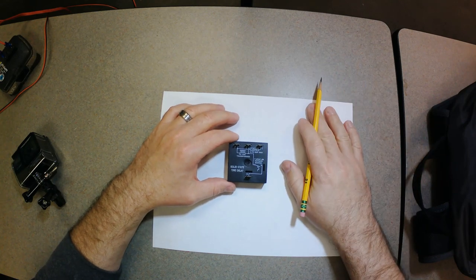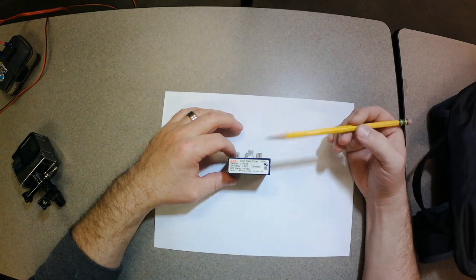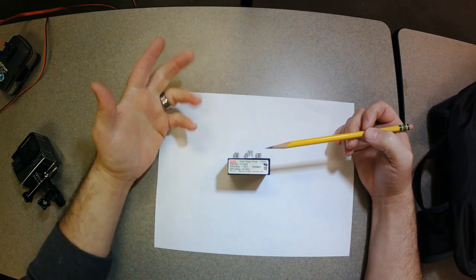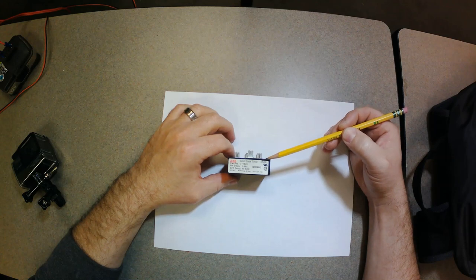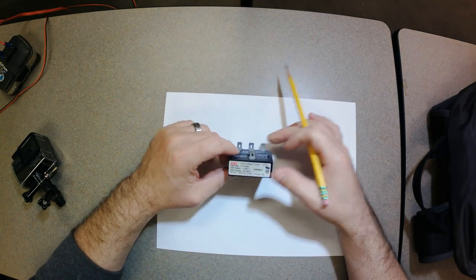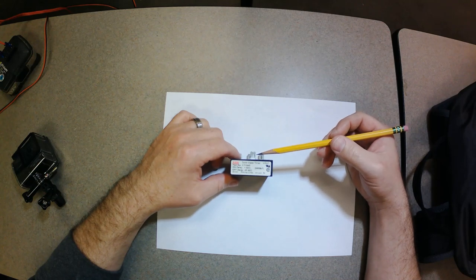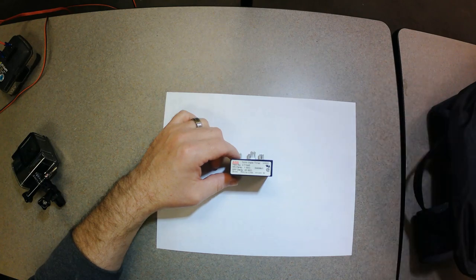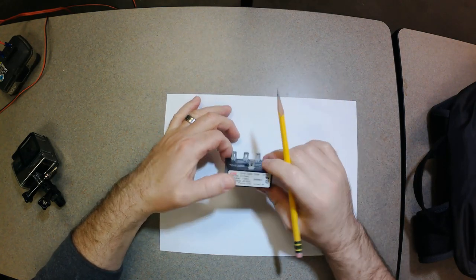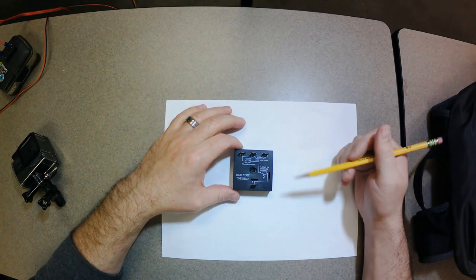I'm going to reinstall this solid state timer and give you a walkthrough. It's got four quarter-inch male terminals. On the side it says solid state timer, CT series - you can look them up. Littelfuse has one, ABB has one, but I believe it's made by SSAC. This is more or less old tech, but at the time it was state of the art. Everything is going solid state now - circuit boards on newer high-efficiency units, mini splits, everything.